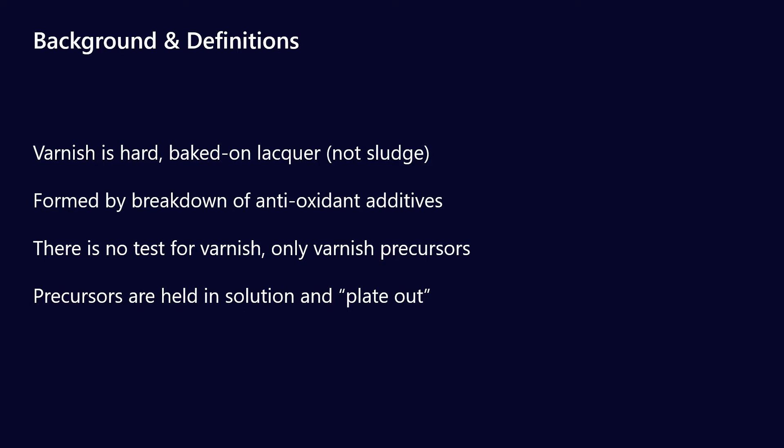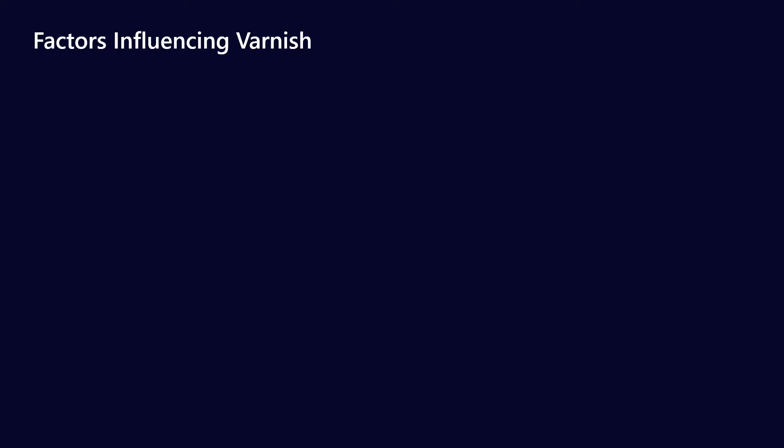Regarding varnish precursors — I'll do another video on the mechanisms of varnish formation — but effectively what happens is you get a breakdown of some of the additives, which gets held in solution for a little while. Then when it finds a cold spot or a low flow area, it comes out of solution and plates out. That's what we're talking about when we talk about varnish.